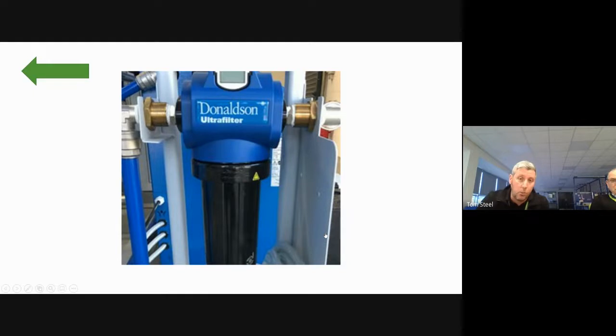If the auto drain doesn't work, if it's not being maintained or replaced as required, then you'll have moisture carryover or you can have oil carryover, which will damage the oxygen generators, which will show up as a purity issue. Also, the filtration elements themselves have to be replaced. If you don't replace them periodically, then they will start to block. And what you'll see is low pressure, which will lead on to purity. And you can see where I'm going with this. Everything leads to the purity being affected.